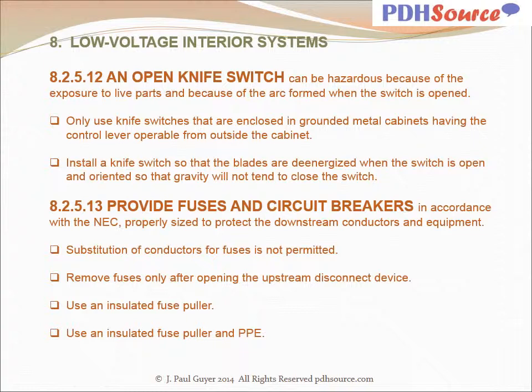Provide fuses and circuit breakers in accordance with the National Electrical Code, properly sized to protect the downstream conductors and equipment. Substitution of conductors for fuses is not permitted. Remove fuses only after opening the upstream disconnect device. Use an insulated fuse puller and personal protective equipment.